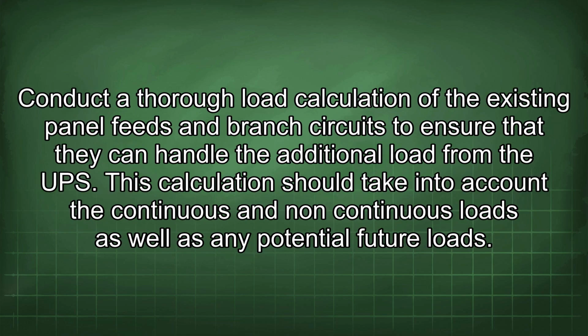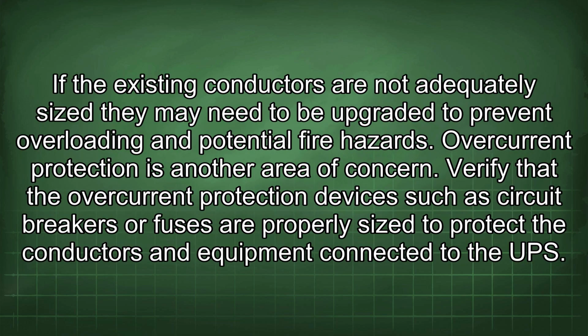Conduct a thorough load calculation of the existing panel feeds and branch circuits to ensure that they can handle the additional load from the UPS. This calculation should take into account the continuous and non-continuous loads as well as any potential future loads. If the existing conductors are not adequately sized, they may need to be upgraded to prevent overloading and potential fire hazards. Overcurrent protection is another area of concern.